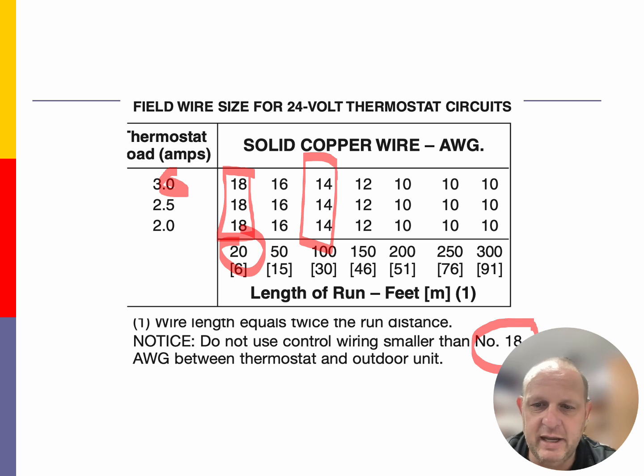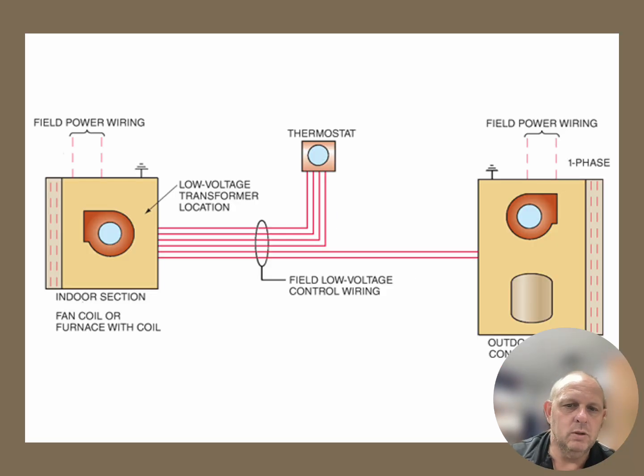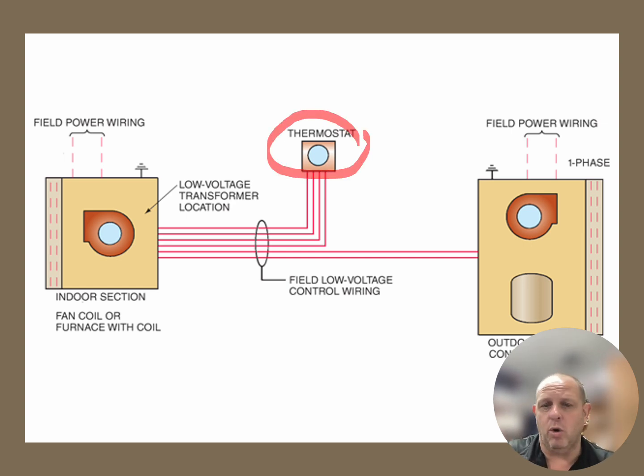So what we're looking at here is the outdoor unit, the thermostat, and then the indoor unit. The way that you are going to run your control wires is every connection that you're going to make has to be made inside the indoor unit. I've seen a lot of my students use the thermostat as the connection point for the outdoor unit and the indoor unit. It works for my class, but it doesn't work for the field because this thermostat is going to be sitting on a wall somewhere 20, 30 feet away. Okay. We're not going to take the wires that are coming from the outdoor unit and run them into that thermostat. That's not the way we're going to do it.